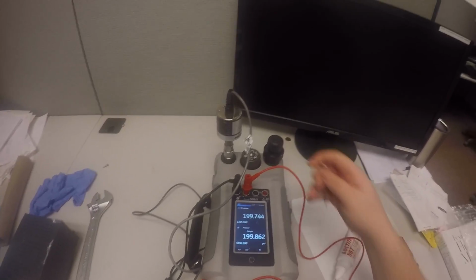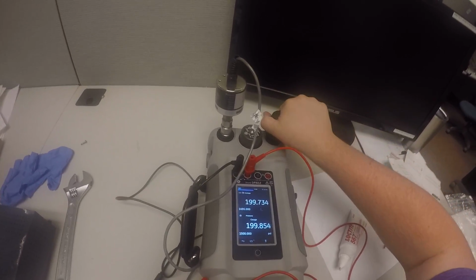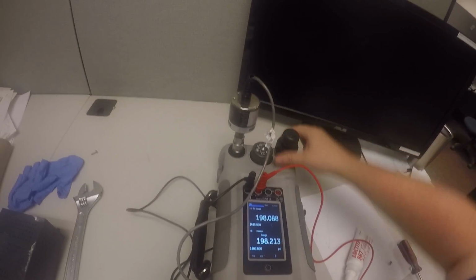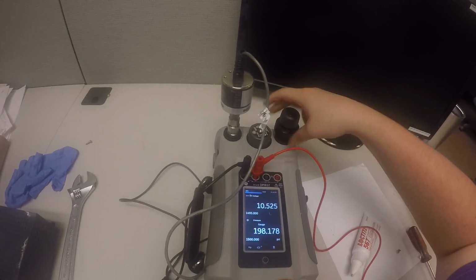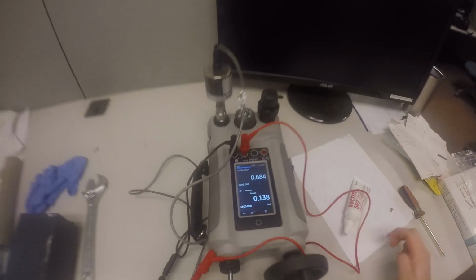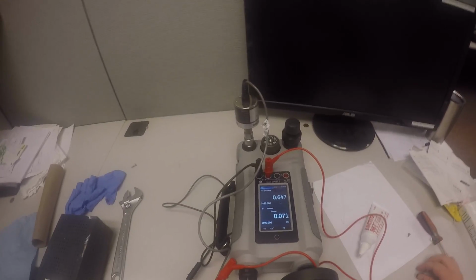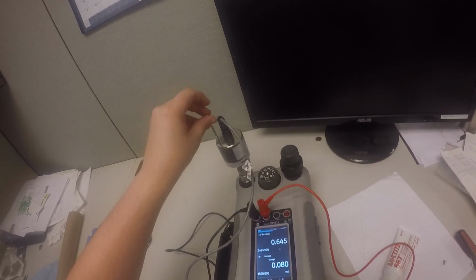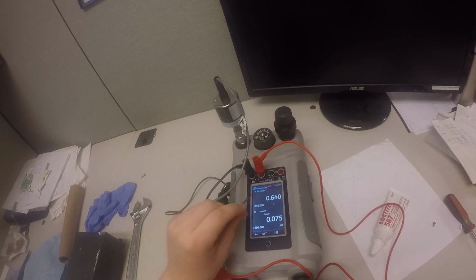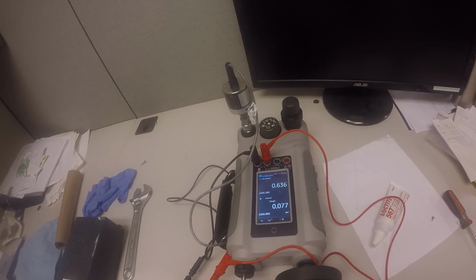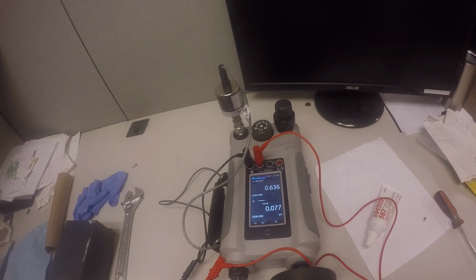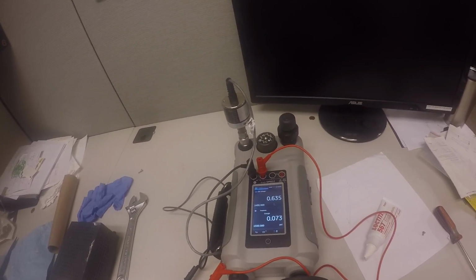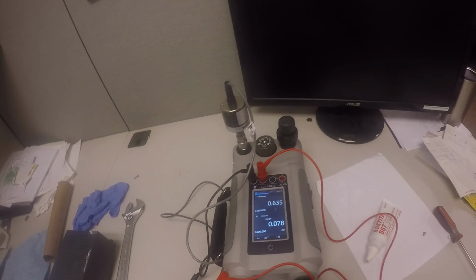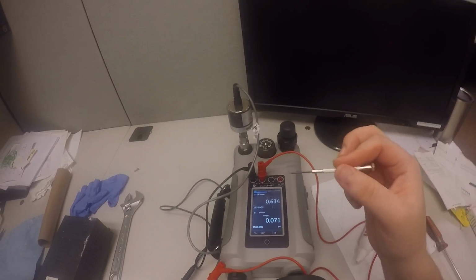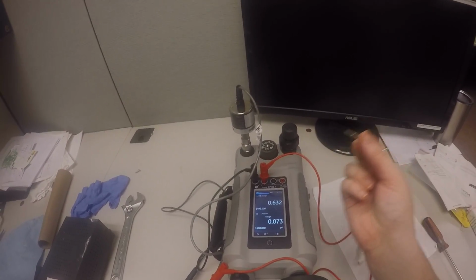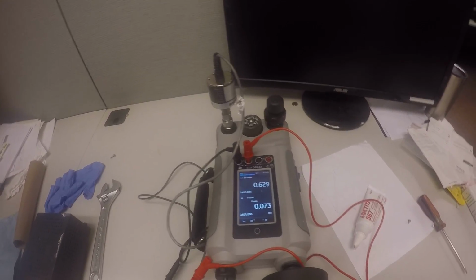Once you complete that, you release the air from the Druck by unscrewing these right here. So now we're back down to atmospheric pressure. Alright, now that we're here, we're going to adjust the 0 screw on the transducer once again. This will show a different pressure measurement than the first time around. And that is due to adjusting the line that is made from the ratio from voltage to pressure that we did. So we need to do a few iterations of this to actually get the right measurements for both. Once you finish that, then you're good to go.